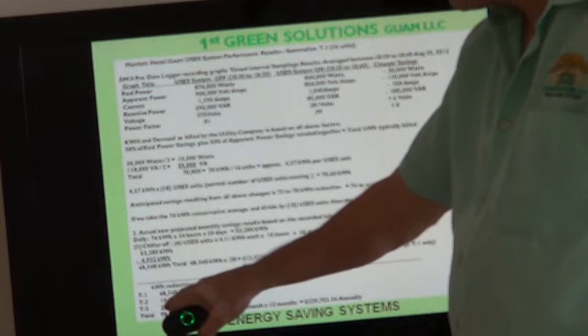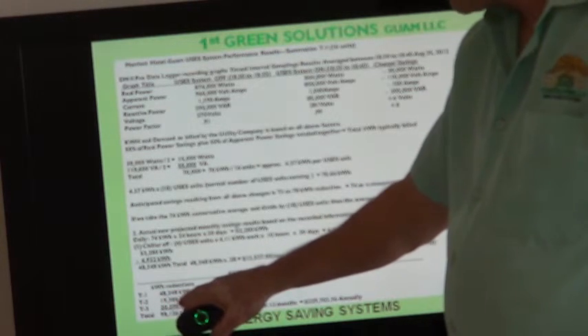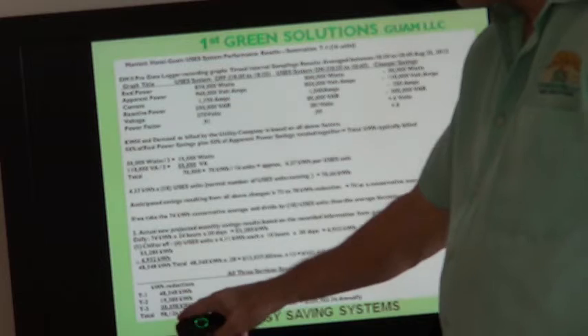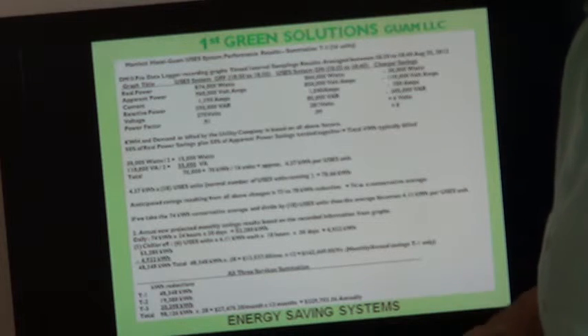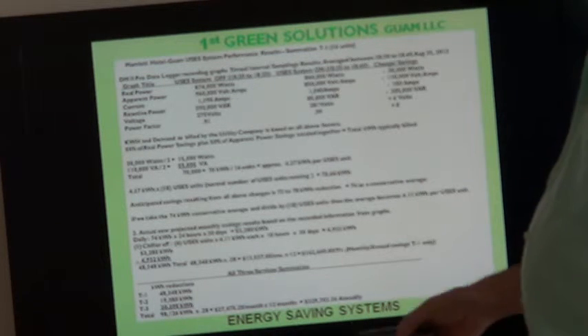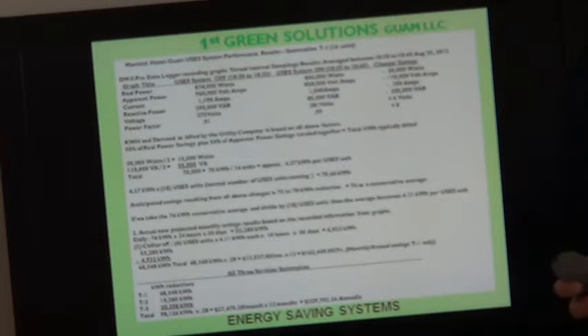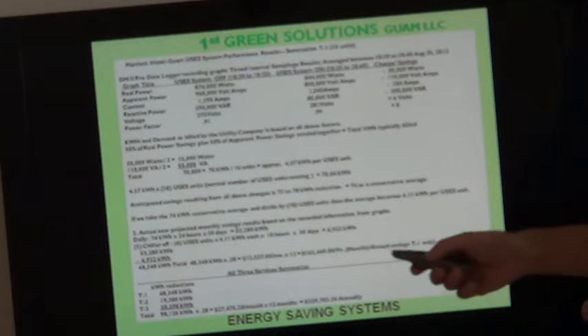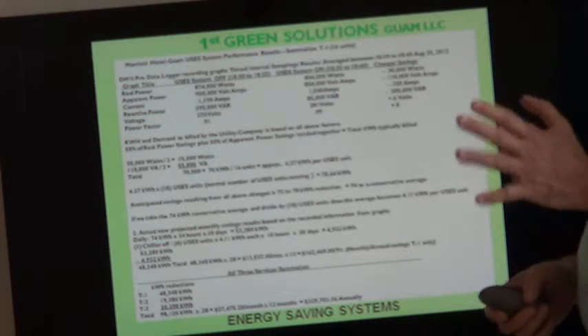The other 2 services, similar readings were taken and summations were performed. T2 is 19,380 kilowatt hours saved, and T3 is 30,398 kilowatt hours saved. Total 98,126 kilowatt hours saved times 28 cents a kilowatt hour, and multiplied times 12 months ends up being roughly $330,000 per year savings for the Marriott. This ended up being significantly more savings than we had projected, reducing their overall ROI to less than 1 year.